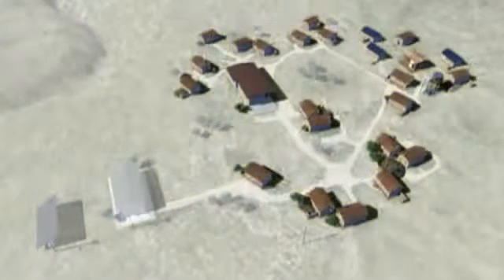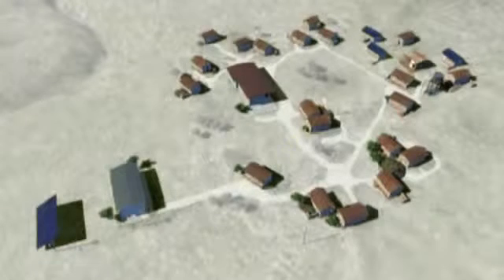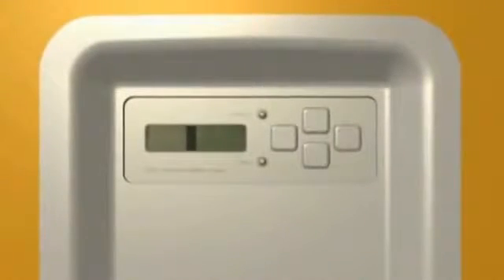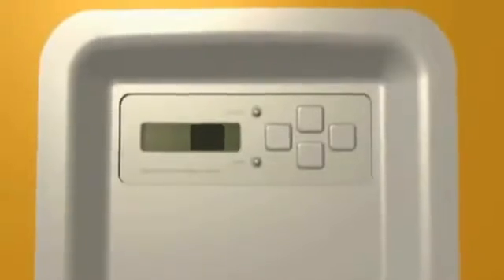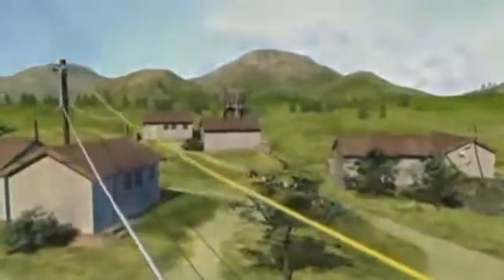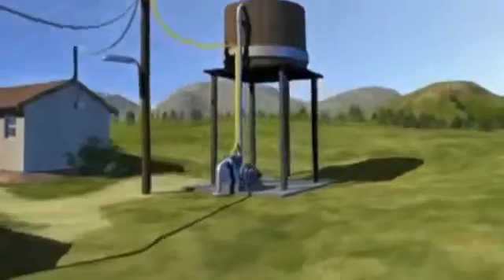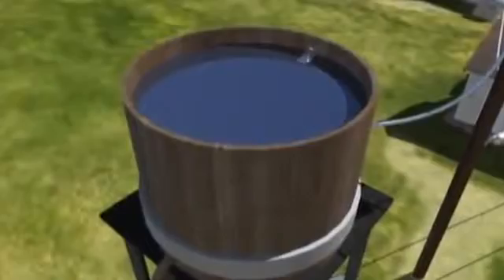Consumers and energy sources alike are coupled in a joint AC network. By minimally altering the network frequency and voltage, the Sunny Island battery inverter can regulate load fluctuations as necessary, in the same way as our public grid does. This means that at times when there is no direct demand for all the electricity available, it can supply special consumers, such as water pumps or refrigeration systems.